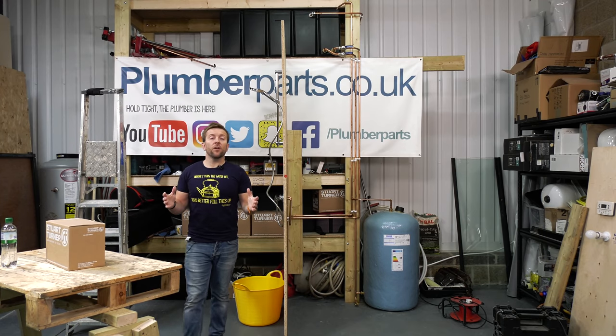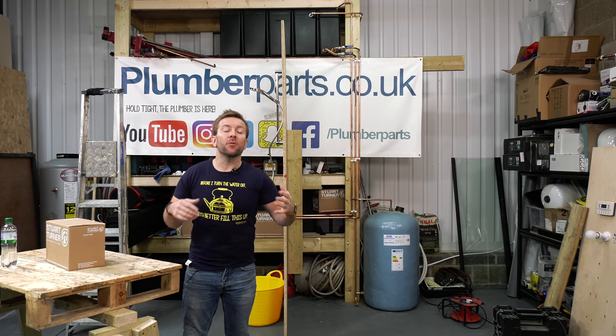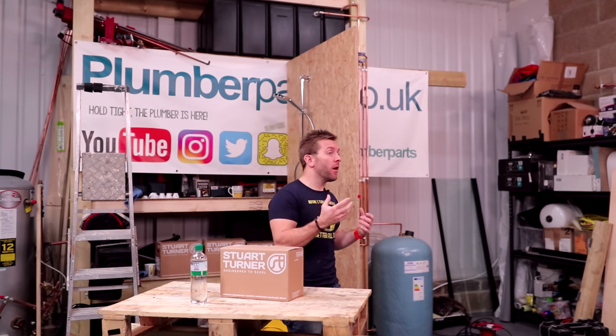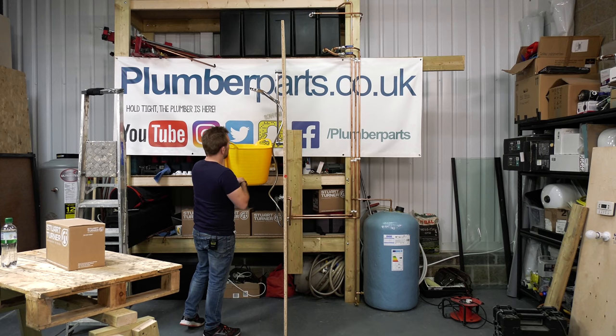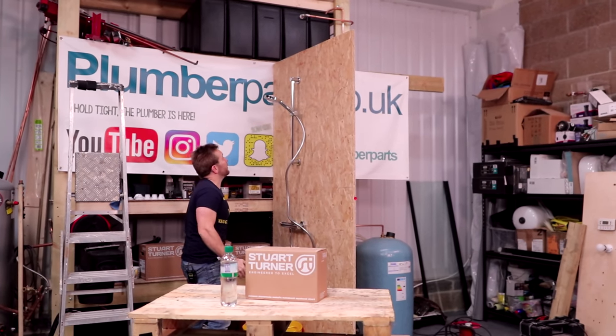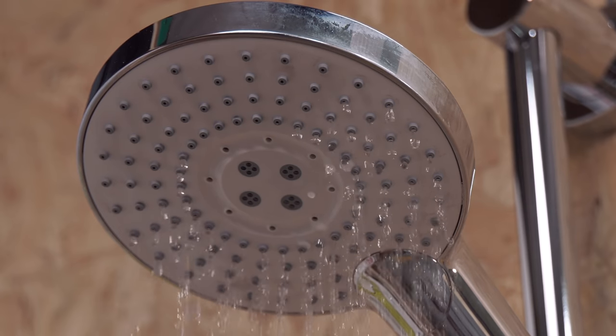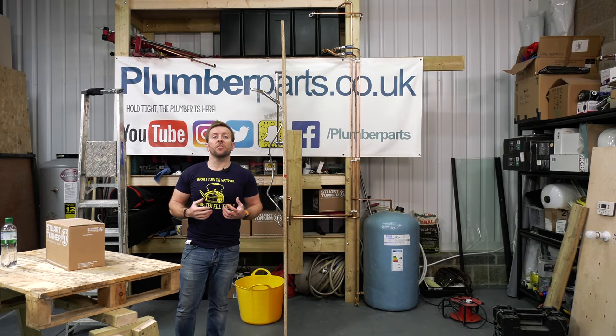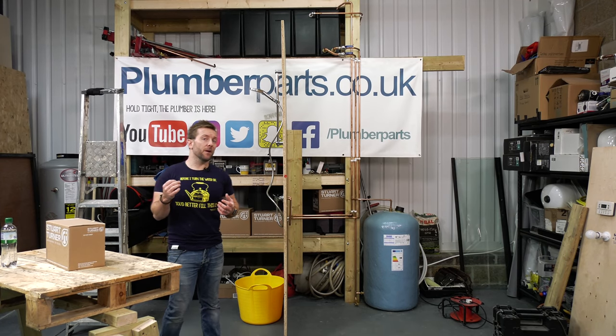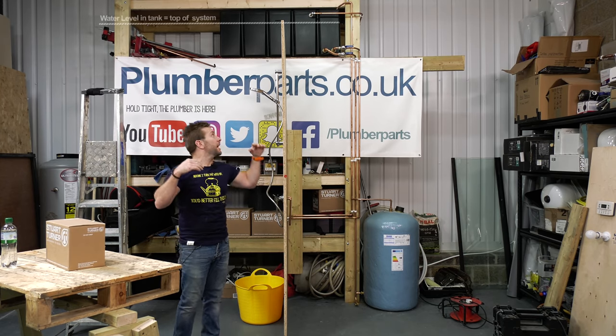So I'll be able to turn on the water now and we should be able to get some water out of this shower head, but we're restricted by the head pressure, which is why I don't think we're going to get a very good performance out of this. So look, there's the performance we're getting at the moment - it's not great, and we have got hot water coming out. You can hopefully see some of the steam rising up. So why have we got this problem? What is going on here? Why have we not got very good head pressure?